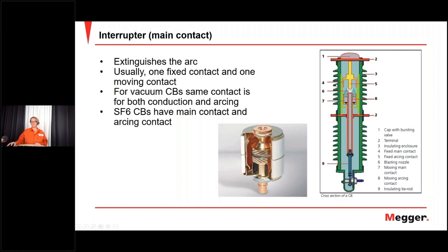In the SF6 circuit breaker, you have a gas which will get compressed during the operation, and it will be used to quench the arcing when it's opening. Also, there will be a temperature rise if there is arcing, which will also make a higher pressure in the gas, which will quench even more. So it's a quite clever solution.